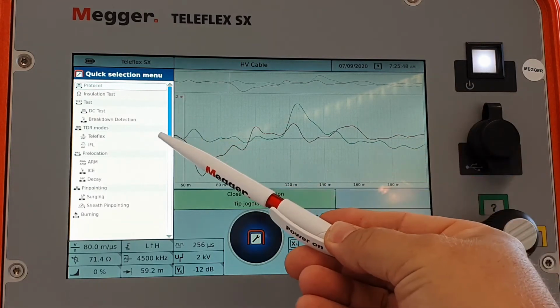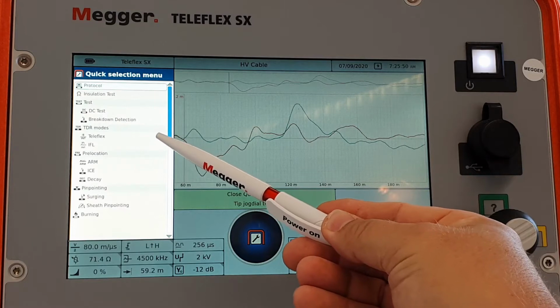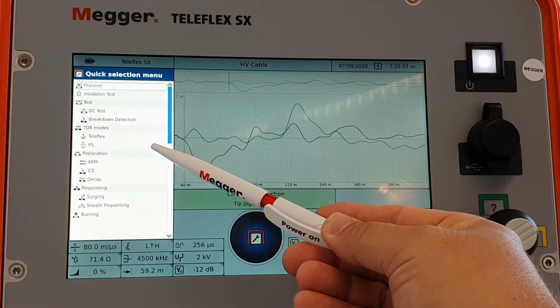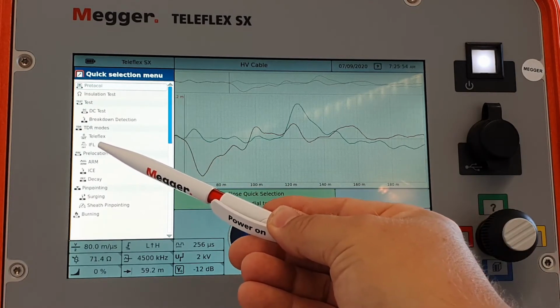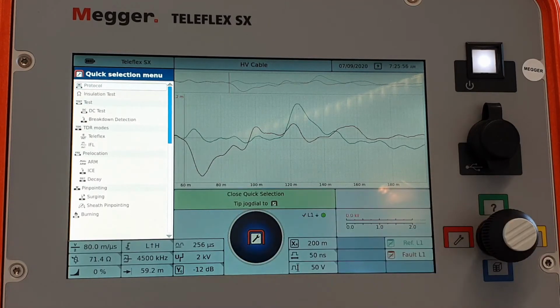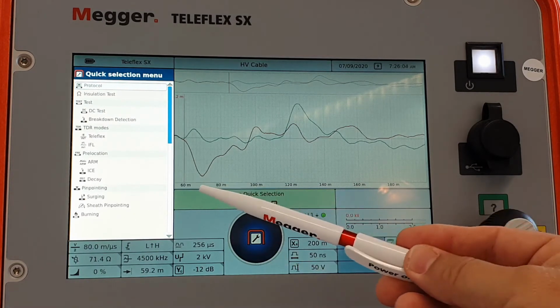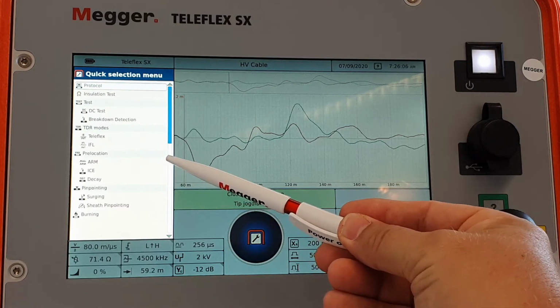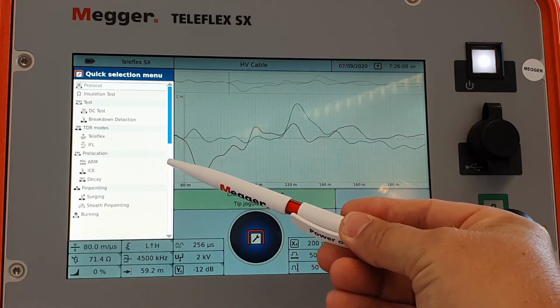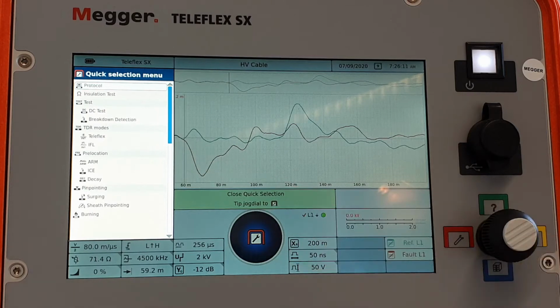Then for prelocation we have the normal reflectometer mode, the teleflex, and a nice variation with the intermittent fault locating mode, which will also save traces for us on the screen as we work with it. This is all not applying high voltage. And here we come to the high voltage methods. Arc reflection method, the most commonly used one. Some people are only using this method. It's the easiest one, the fastest, the clearest.